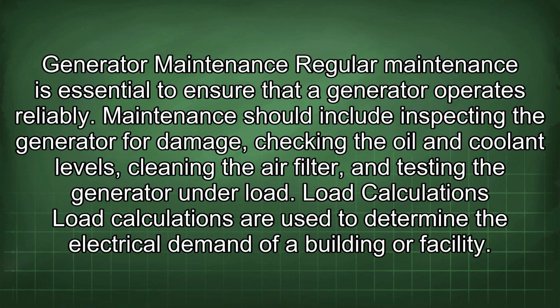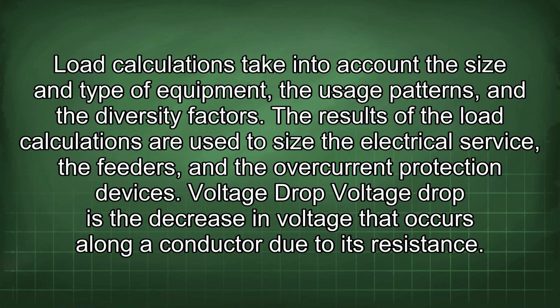Load calculations. Load calculations are used to determine the electrical demand of a building or facility. Load calculations take into account the size and type of equipment, the usage patterns, and the diversity factors. The results of the load calculations are used to size the electrical service, the feeders, and the overcurrent protection devices.